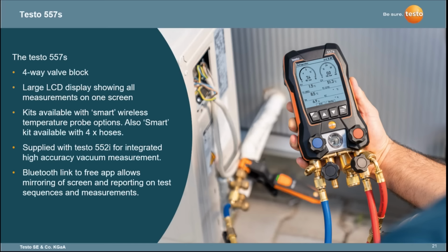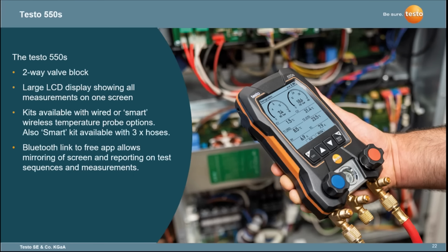We do kits that are available with and without hoses, for example. The 557 is always supplied as a kit with the 552i vacuum probe. So you've got this integrated high accuracy vacuum measurement straight out of the box. We also do the 550s, which is just a 2-way manifold design. Again, it's compatible with the same probes. There's smart kits available. The 550s doesn't come as standard with the 552i vac gauge, but if you want to add it in at any point, you literally just need to purchase a 552i and it will connect via Bluetooth. It's just not supplied as part of the initial kit.